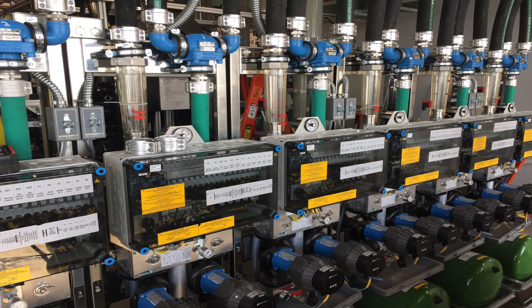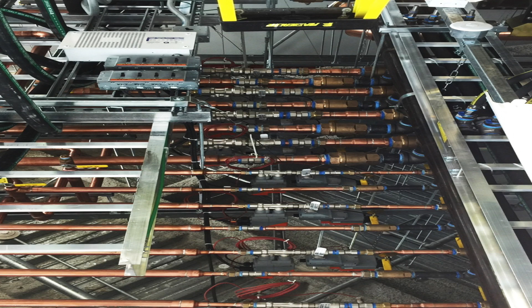Just some of the pumps as they were being set up. What we also did above the top, you'll see some green flashing lights if you look up above the transmitters on the active ones. We have energy valves on it. These modulate the water. We keep the delta from inlet to outlet temperature of 10 degrees so that we're not wasting water up on top. We're supplying what's needed, no more, no less.